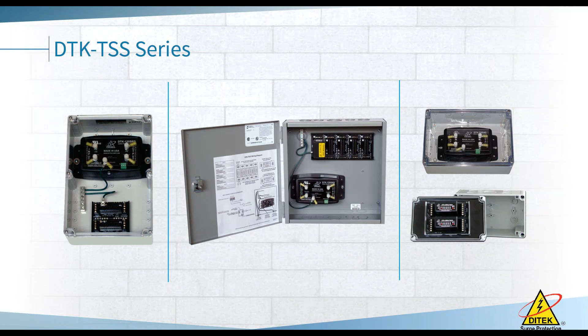Networking communications surge protection. We've got different platforms you'll see at the top: a 6-channel on a hinged wall bracket and a 12-channel on the left for a 19-inch rack. These come empty except for a bag of blanks like you see on the left, with ports 1 through 4 having blanks in them for a clean install. These are where you can mix and match different modules. You could have IP, PoE, maybe a digital extension phone, an analog phone, a speaker, or BNC. So it's basically mix and match, build as you go. Instead of having 6 or 7 different devices mounted on a back plane somewhere in a cabinet or closet, you can clean it up, put it all in one chassis with a single point ground, giving a cleaner install to work with and to service later.